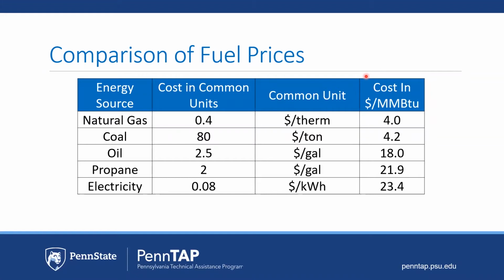Note that although coal is a fairly inexpensive heating source, there may be significant costs associated with it. For example, you may have to pay an employee to operate a boiler all day to make sure that the fire is constantly going in the wintertime and that the fire does not go out. This labor cost can add tens of thousands of dollars, and in many cases will make other fuels, which although expensive, cheaper in the long run. Understanding your fuel options will help you understand how you can possibly save more money if you have the opportunity to convert your equipment or to upgrade to a different fuel type.